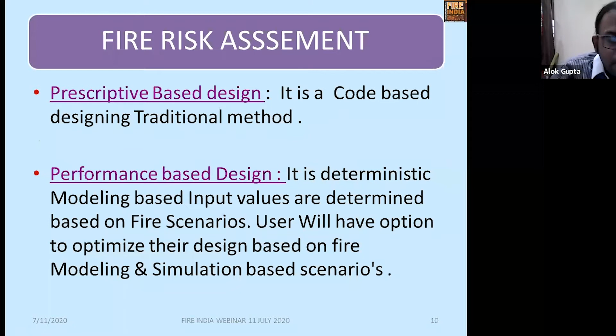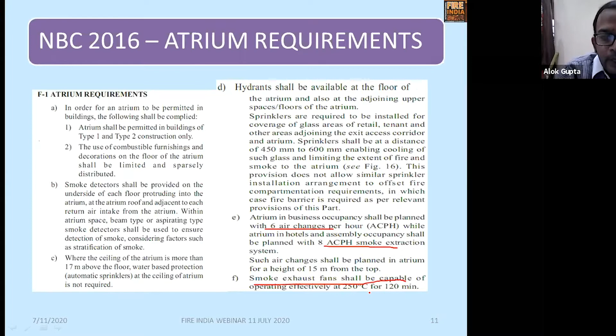I'm taking, in today's discussion, the example of a commercial building, which is very popular in Delhi. This is a building which has an atrium, and these are the NBC requirements for the atrium, as described in NBC 2016 and Annexure F. For the ventilation side, NBC says it has to have 6 air changes or 8 air changes and a smoke extraction system, and the smoke exhaust fan shall be capable of 250 degrees Celsius for a fire rating of 120 minutes.